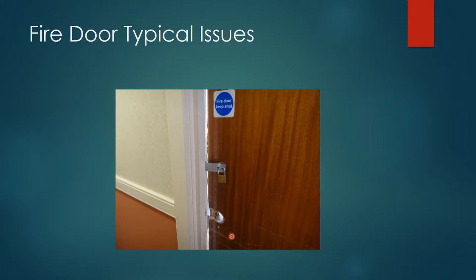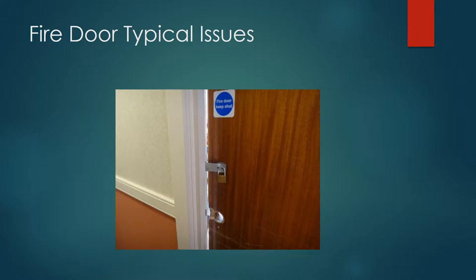Actually, it says 'fire door,' so it is meant to be a rated door. It has been modified significantly and certainly would not pass any kind of inspection. The next example — initially your eyes are drawn to obvious damage on the door, and very likely that would be an issue because it is definitely a damaged door.